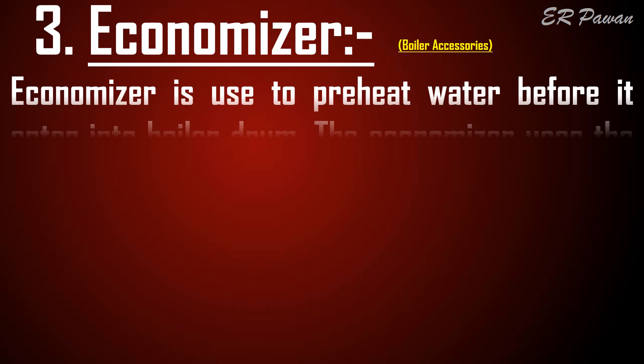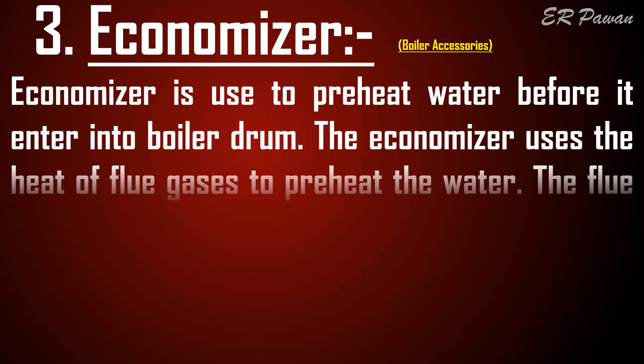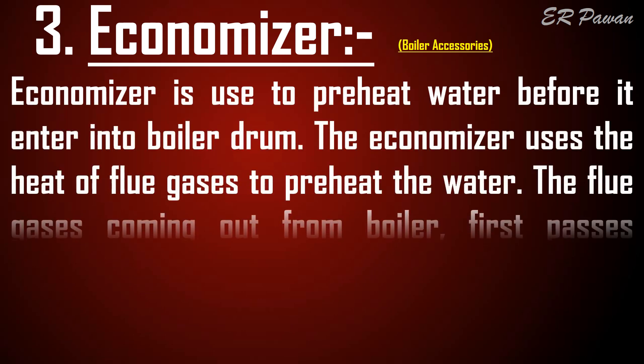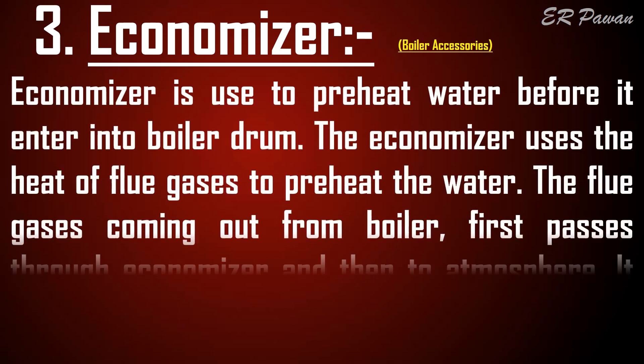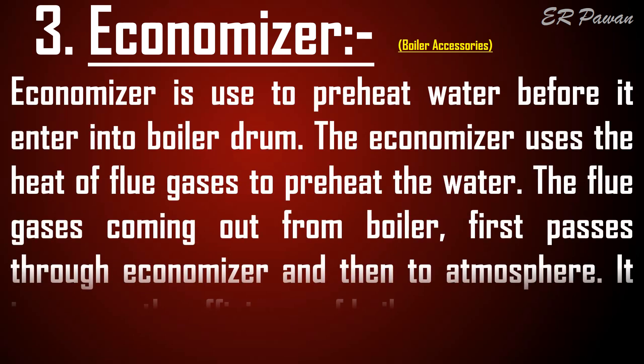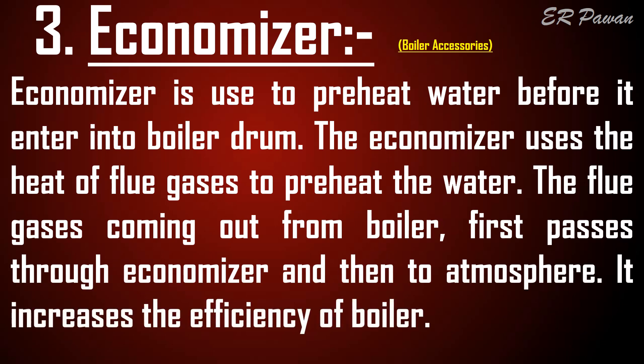Economizer. An economizer is used to preheat water before it enters the boiler drum. The economizer uses the heat of flue gases to preheat the water. The flue gases coming out from the boiler first pass through the economizer and then to the atmosphere, which increases the efficiency of the boiler.